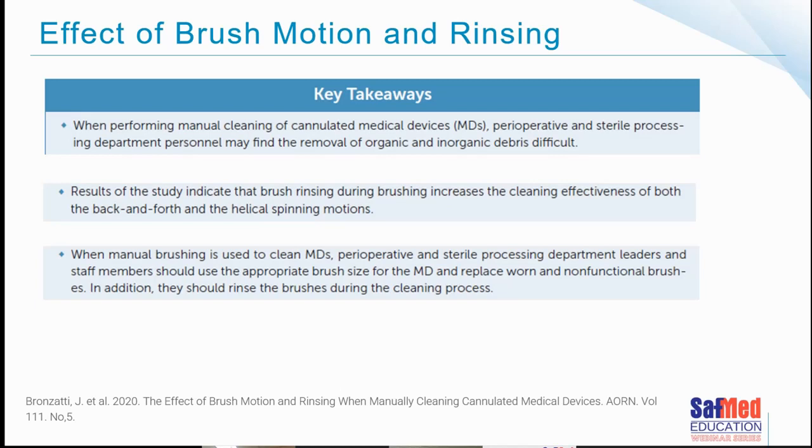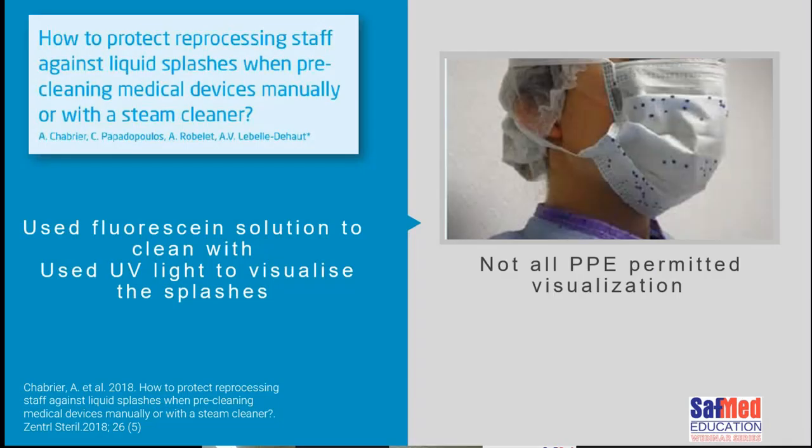The results of the study indicate that brush rinsing during brushing increases the cleaning efficacy, and that when manual brushing is used, the department members should use the appropriate size brush for the lumen and replace worn and non-functional brushes. In addition, they should rinse the brushes during the cleaning process. All good information.